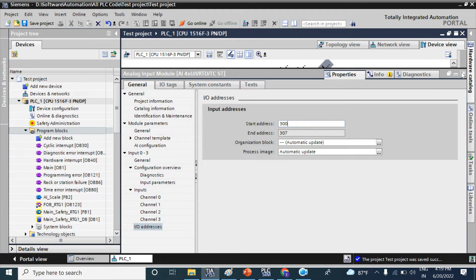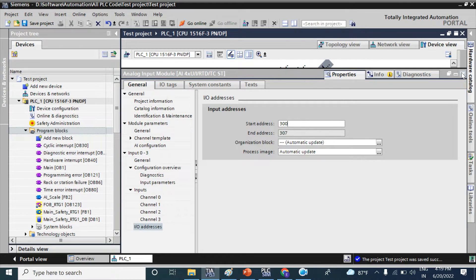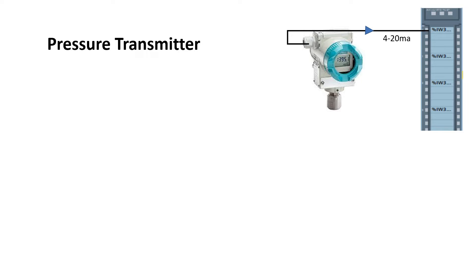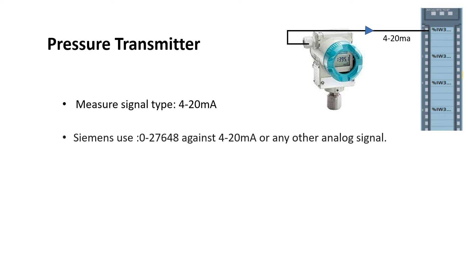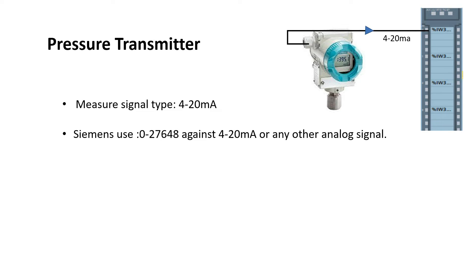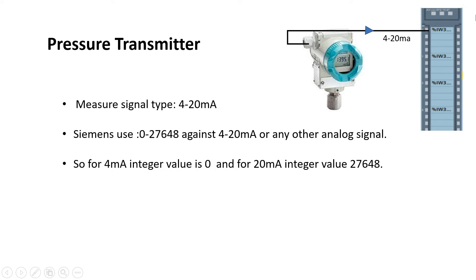Keep in mind that your analog input signal address is 300. Now if you connect a pressure transmitter with a measuring signal 4 to 20 milliamp, then your measuring signal 4 to 20 milliamp will convert in integer 0 to 27648 in the analog module.